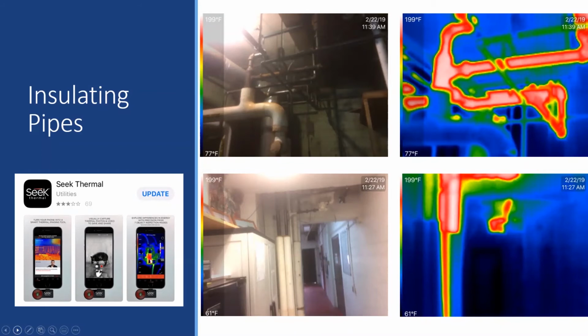From these images, we can see that the exposed uninsulated piping is nearly 200 degrees Fahrenheit, and the piping that is insulated, covered with the white insulation, is normalized to the conditions of the room. There were several examples of exposed piping within this facility. If this facility were to insulate these pipes, it is estimated they could save $1,400 per year.